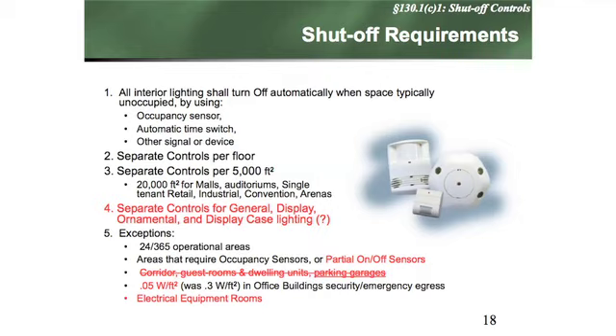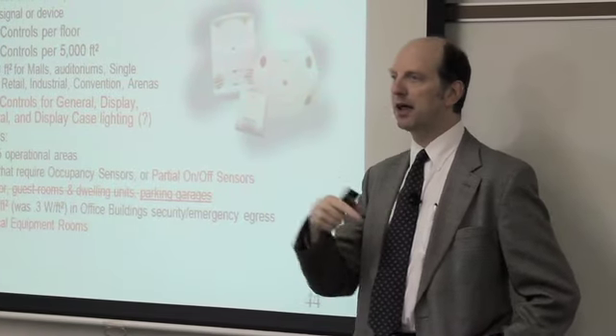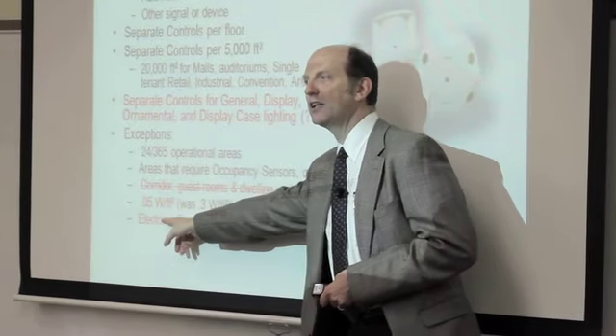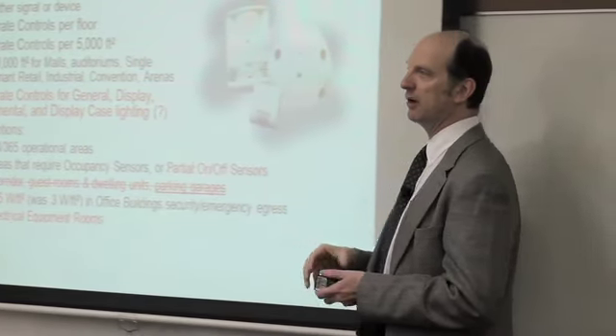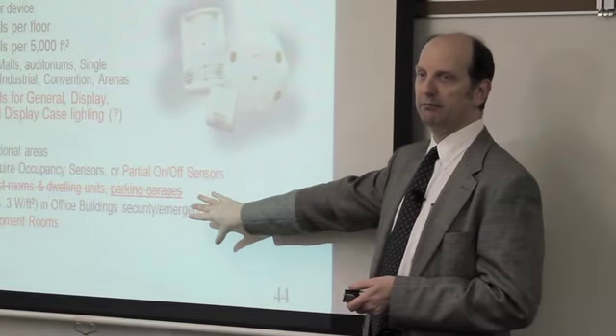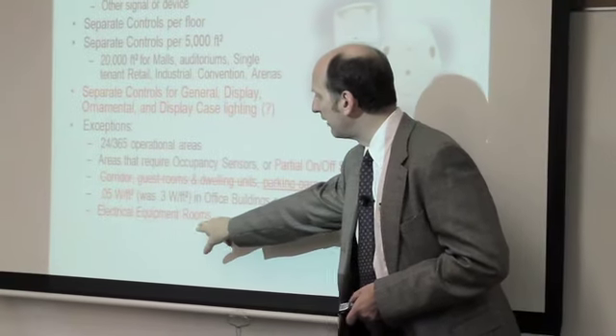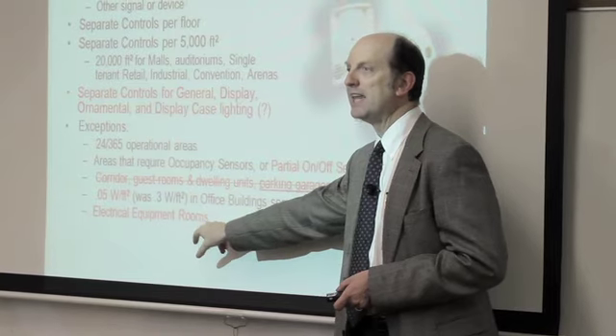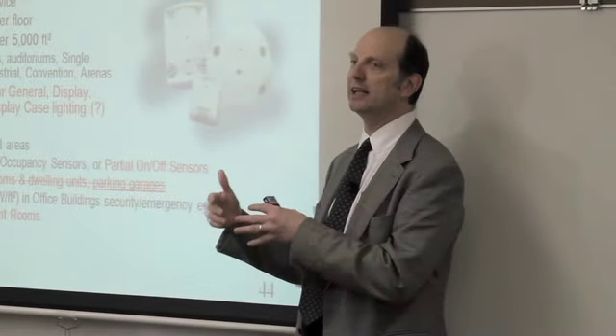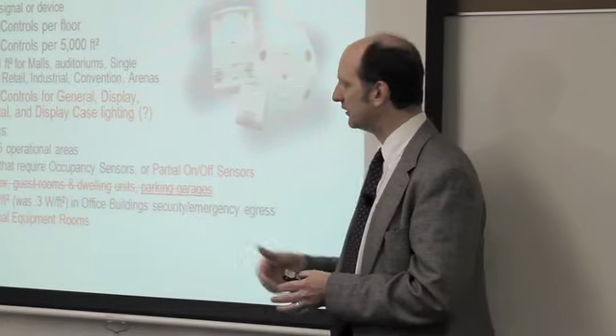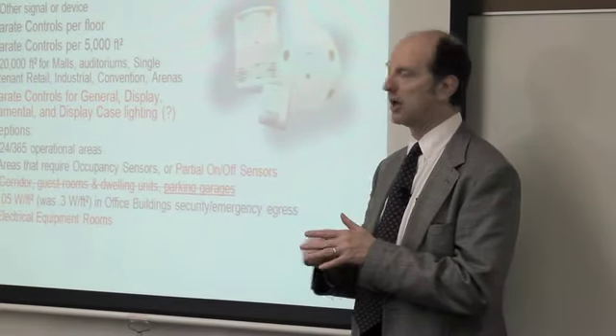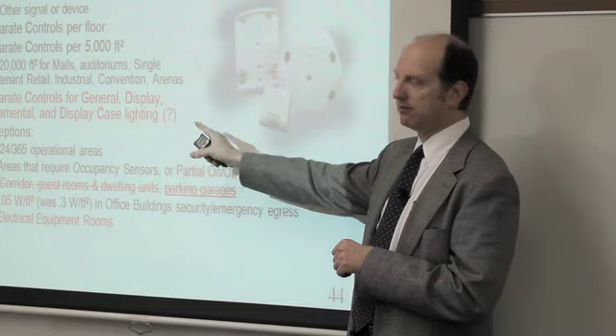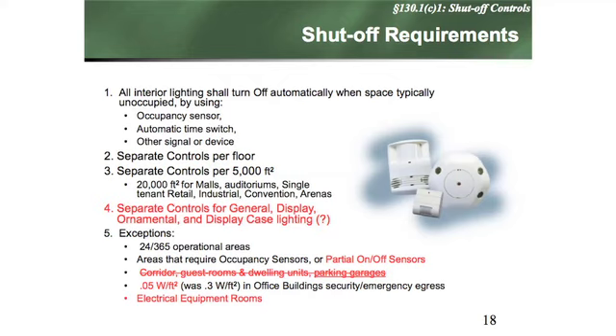Egress lighting, security lighting in a building used to be 0.3 watts per square foot. Pretty high, so you could have a lot of stumble lights that would be on 24 hours a day, never go off. They've reduced that down to a sixth of that. You only have 0.05 watts per square foot to put in security and egress lighting. And somebody actually read the electrical code and figured out that the code prohibits having automatic means only in an electrical closet. NEC prohibits that under, I think it's 110.26(D). So they added that to the list of things. So what you're doing isn't so much different, but where you're doing it is going to start changing.